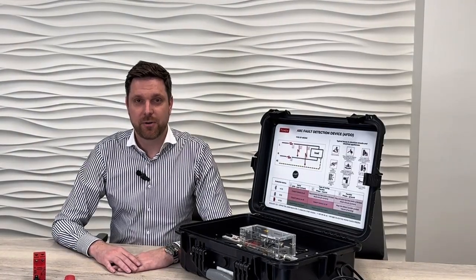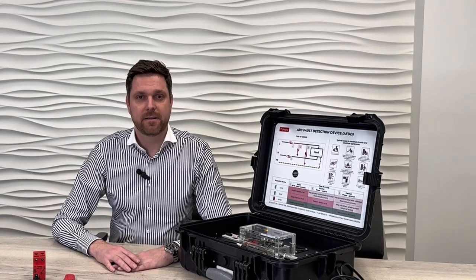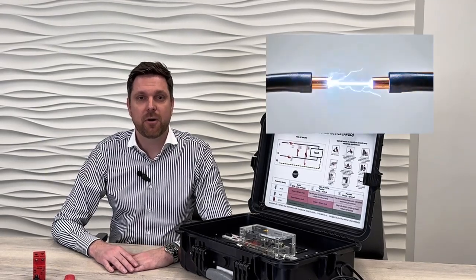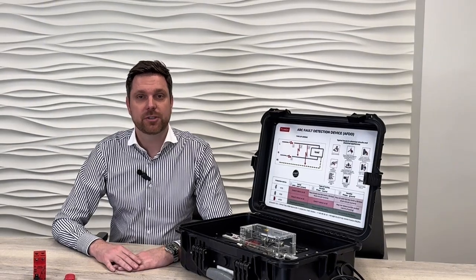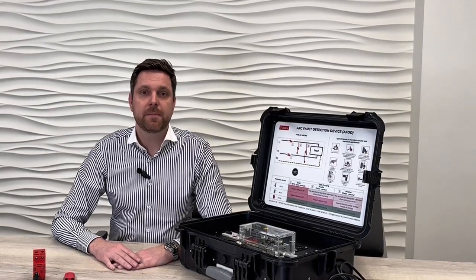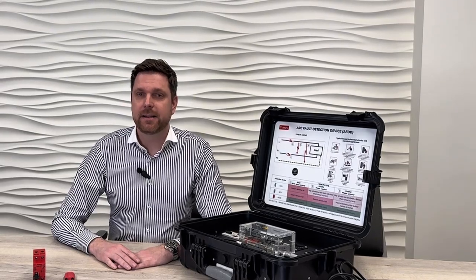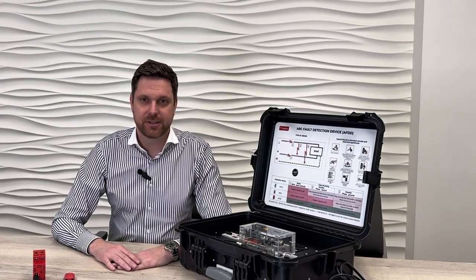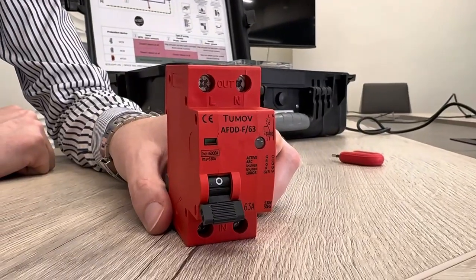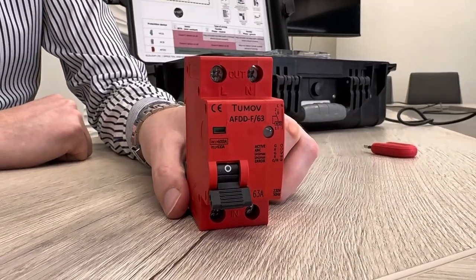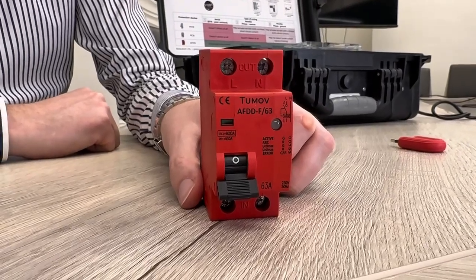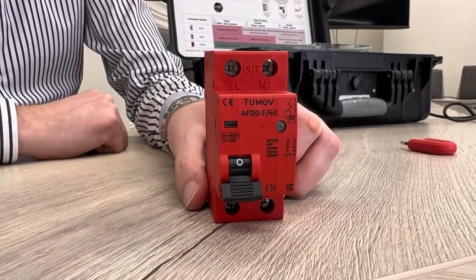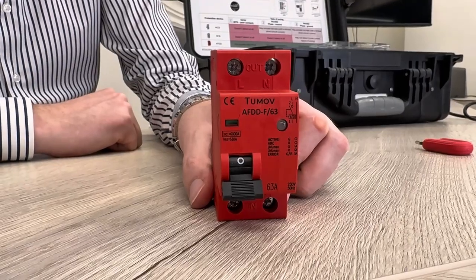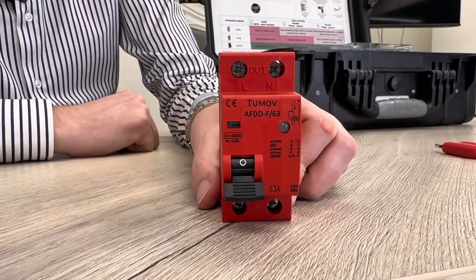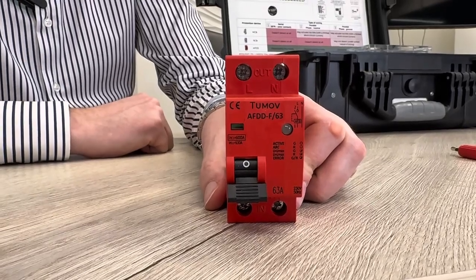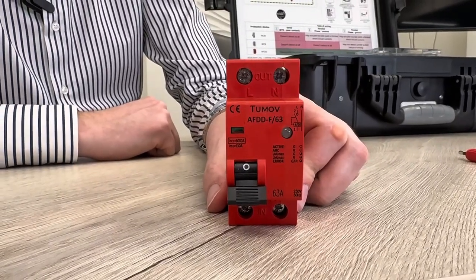Enter the villain of our story, arc fault. Formally defined, an arc fault or sparking is the formation of an electric discharge between conductors. This phenomenon is accompanied by intense light and heat, leading to cable insulation destruction and potential ignition. The good news, there is a superhero in town, the arc fault detection device, or AFDD. The nifty gadget is already mandatory in the United States, Canada, Germany, Austria, Slovakia, New Zealand, the United Kingdom, and Russia. Different rules, the same mission, to put out electrical fires before they even start.